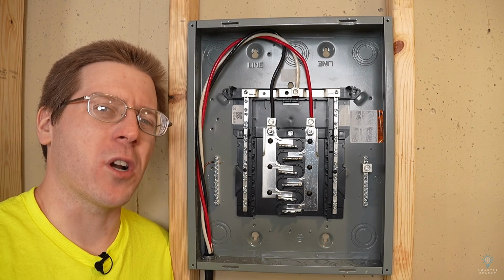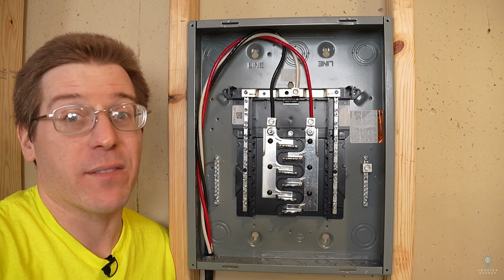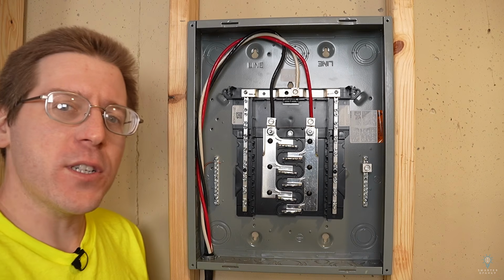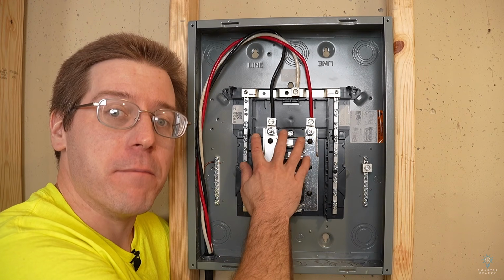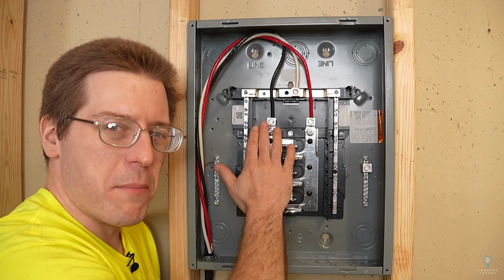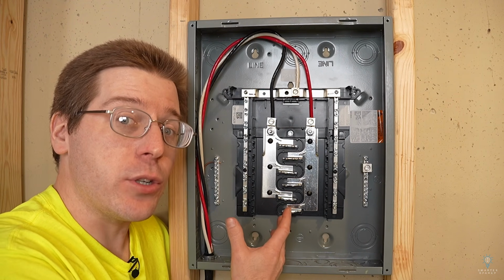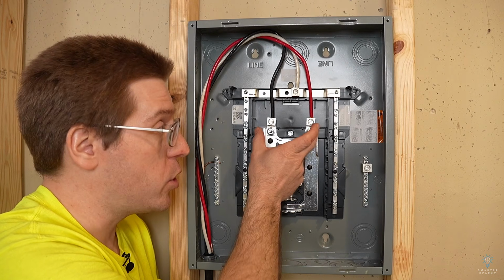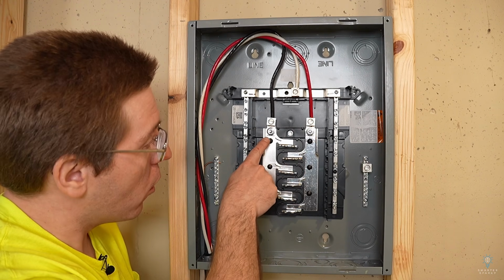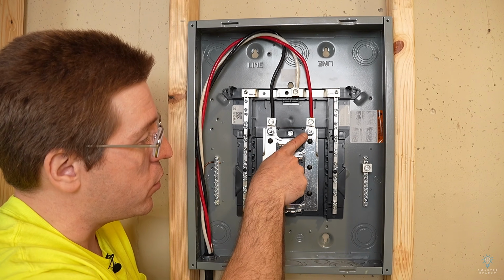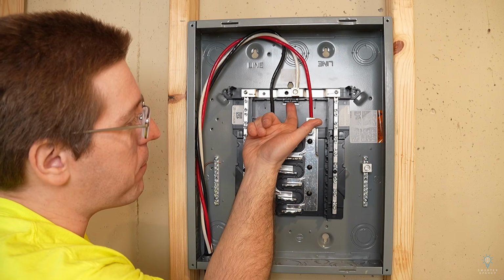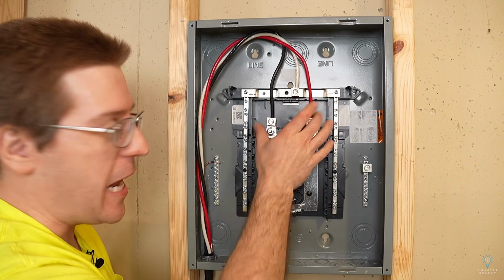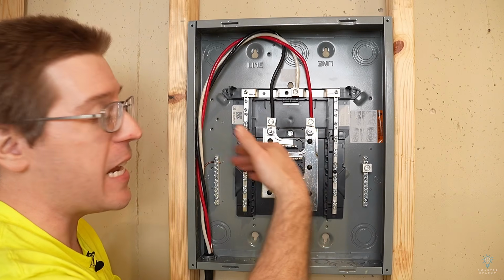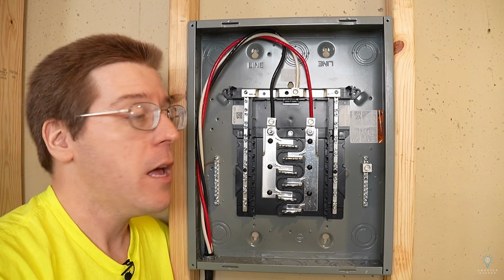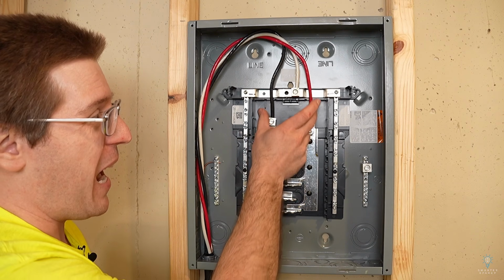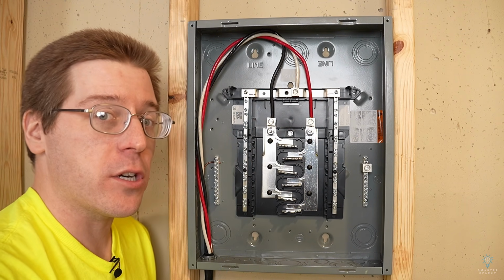I want to talk about 2 more technicalities real quick inside of really any electrical panel. First, I want to address this concept of main lug. Notice there is no main breaker here. You can actually go out and buy a kit to install a main breaker here. Really, all you do is undo these 2 nuts right here, and then there's a clip right up underneath. The breaker just snaps in, you put these 2 nuts back on, and now you've got a main breaker panel. So all this is just bypassing the need for that main circuit breaker.